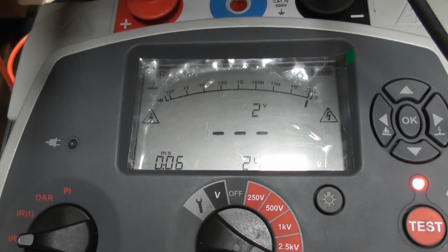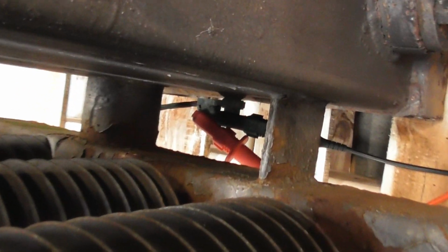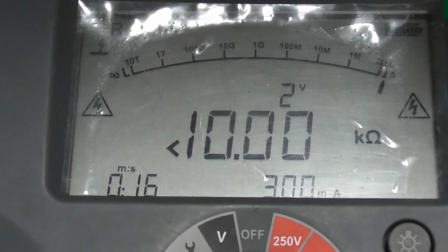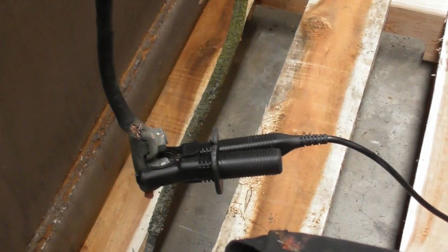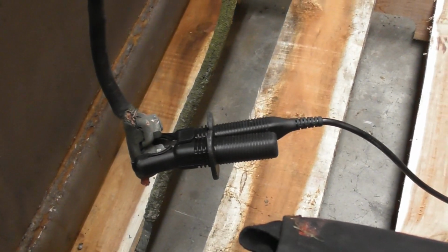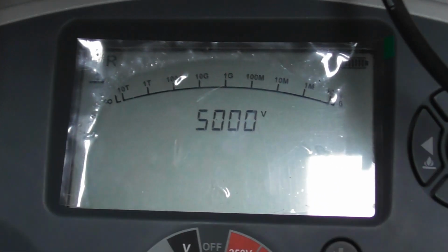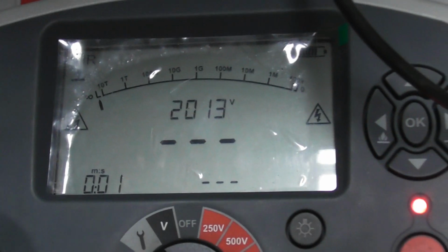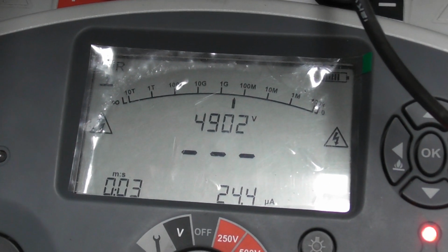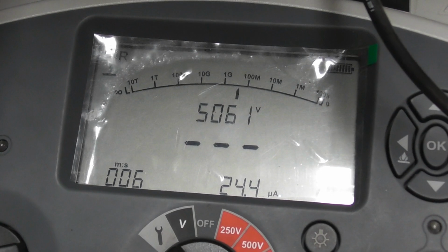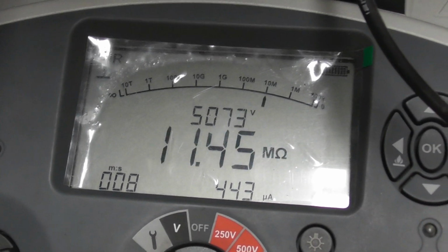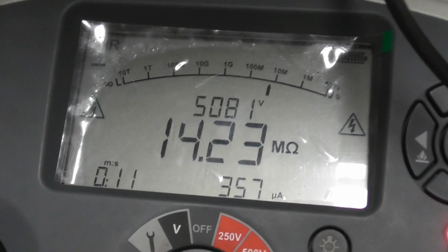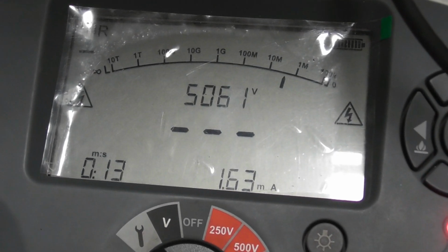Just going to do an insulation test on this transformer. Before you test, check your leads. Connect them both to the same point so you know the leads are making contact in the meter. And then do the test. Will be a 5 kV test. Delta winding. Start the test. The readings will get out of the thing. Holding 5 kV at the moment. 14 megs, lowish.